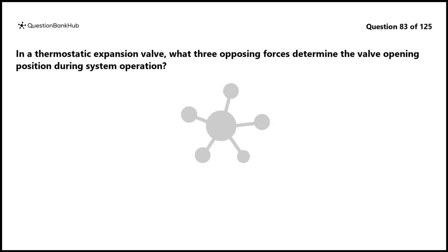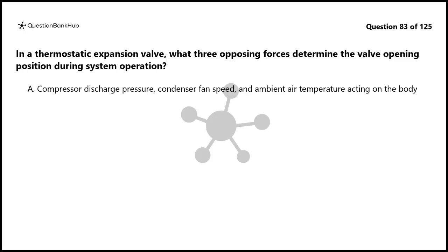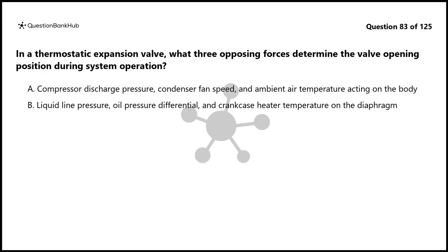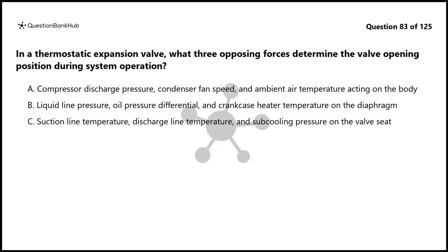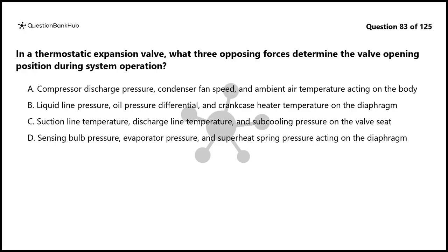Question 83. In a thermostatic expansion valve, what three opposing forces determine the valve opening position during system operation? A. Compressor discharge pressure, condenser fan speed, and ambient air temperature acting on the body. B. Liquid line pressure, oil pressure differential, and crankcase heater temperature on the diaphragm. C. Suction line temperature, discharge line temperature, and subcooling pressure on the valve seat. D. Sensing bulb pressure, evaporator pressure, and superheat spring pressure acting on the diaphragm.